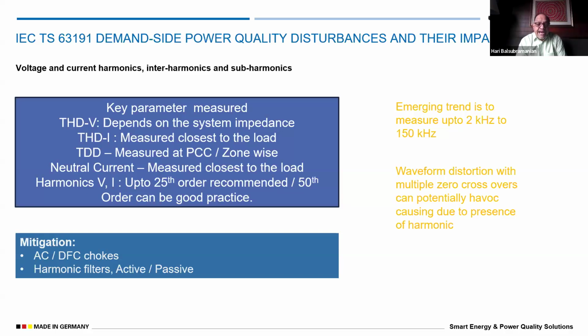Now there is also TDD, which is measured at the point of common coupling for the consumers. This point is not in the standard system, but I have added it as TDD. It should also be measured at least at the PCC, so that we know where we are standing. Then for neutral current measurement, harmonics up to the 25th order are recommended. The 50th order can be a good practice. So we need to know.